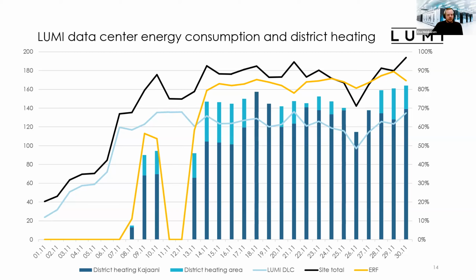This is Lumi's direct liquid cooled cabinets power. So this includes only the liquid cooled partitions of the IT load, and this is the total consumption. Total site power consumption. And this yellow line is the energy reuse factor. So how many percent of the energy that we are using are we able to utilize for the waste heat. And as you can see, when we got our heating production pretty stable, we are able to provide more than 80% of used energy. We are able to reuse more than 80% of used energy back to district heating. And this is something that we are still optimizing. So heat production is still, we are doing fine tuning on the system to find out the perfect parameters to run the district heating on the Lumi.